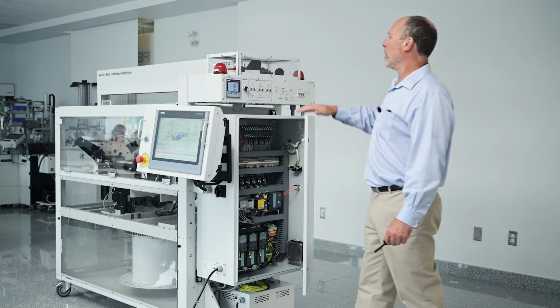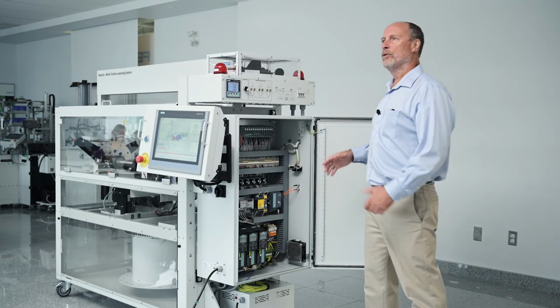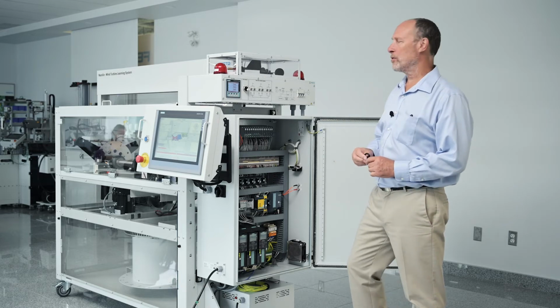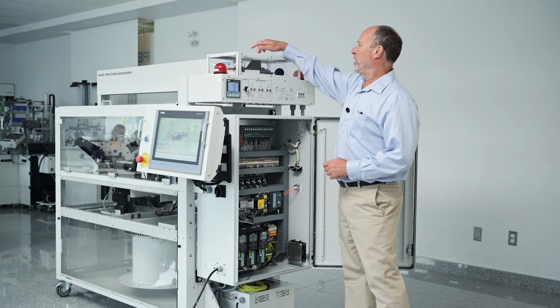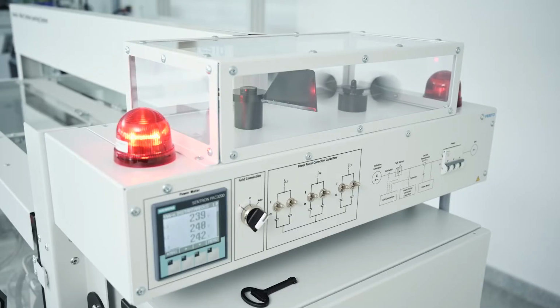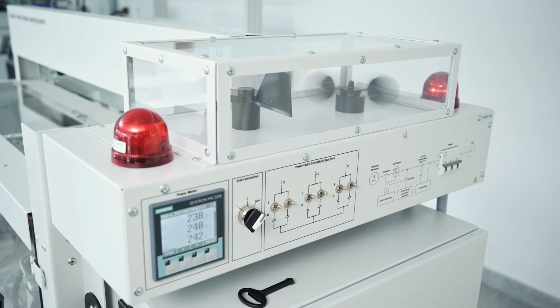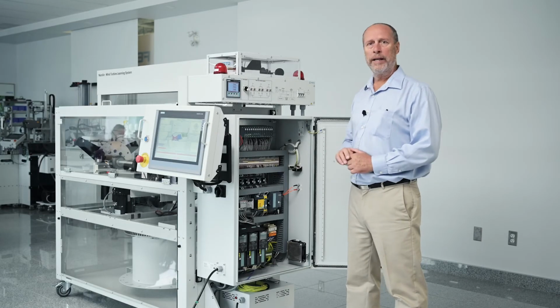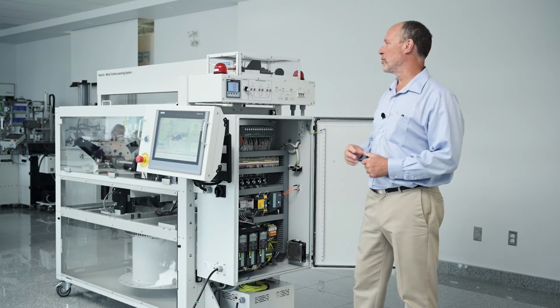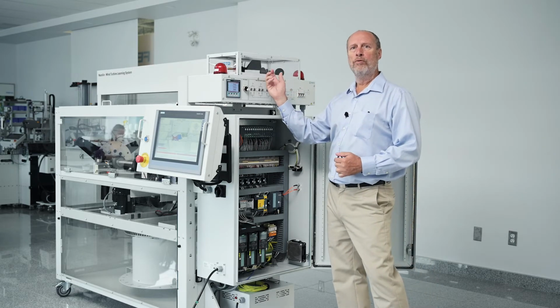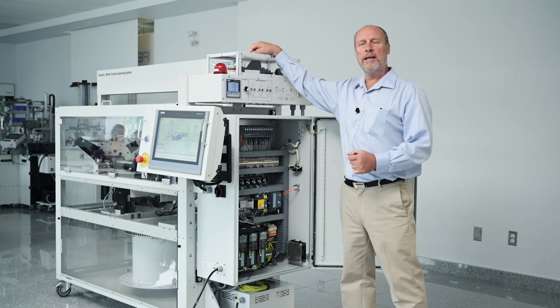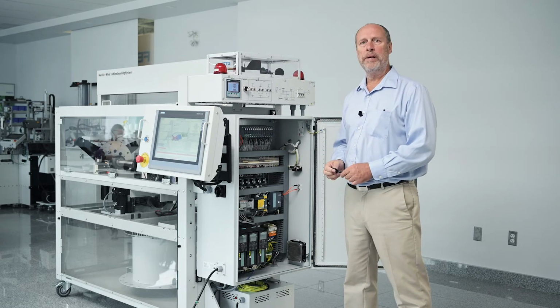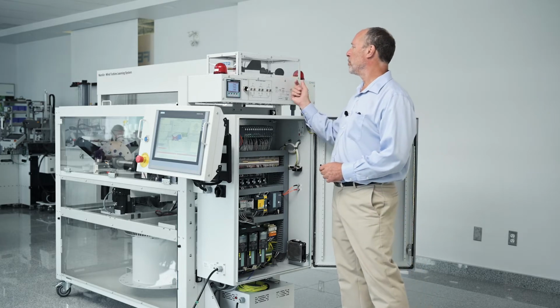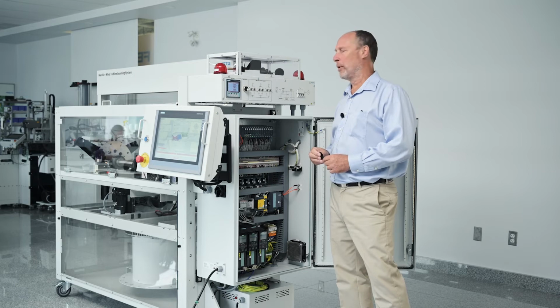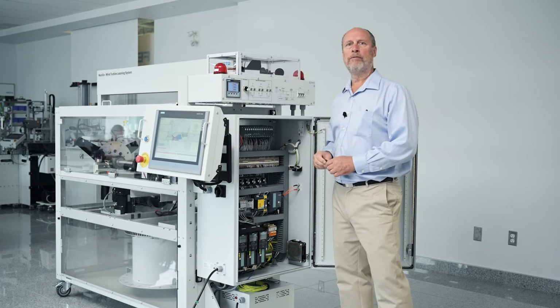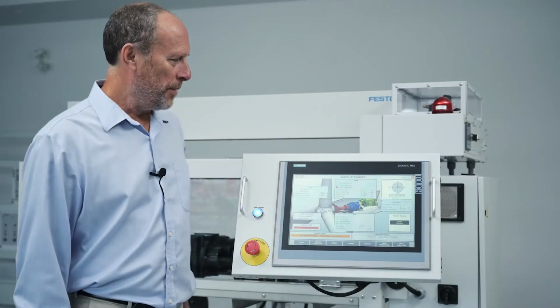On top here, you have the wind element. So the nacelle works with sensors. So you have the wind vane that tells you the wind speed and wind direction, okay? In this case, as I said at the beginning, there's no wind, so we simulate these sensors. So we put a small motor and we move these, but the sensor will send a signal directly to the PLC. So we simulate the motion, we drive this with a small motor, and we take the reading directly from the sensor. Now to the HMI.